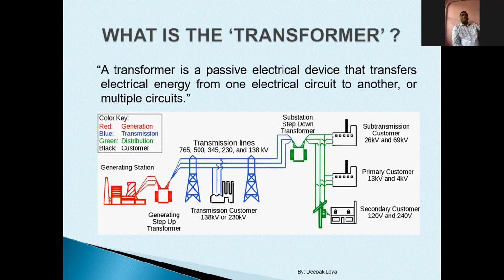The primary voltage of the distribution network is 11,000 volts, that is 11 kV. And from there, what do you need? You need 433 or 415 volts for allowing you to use that power, which is distributed by the distribution network at 11 kV. You need a transformer, and that transformer is stepping down. So those are the terminologies we use: step up and step down.